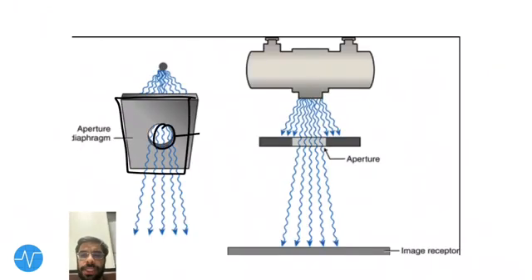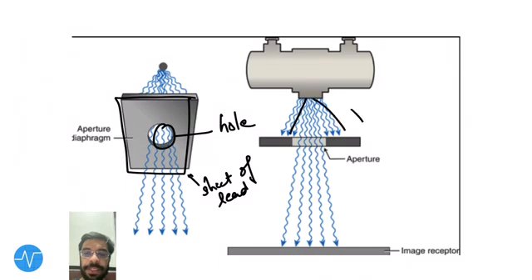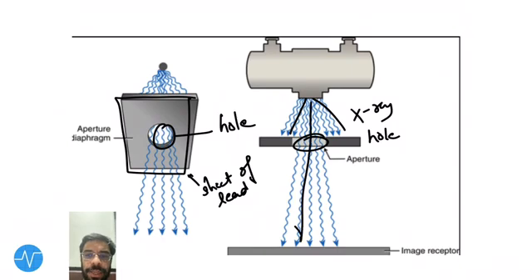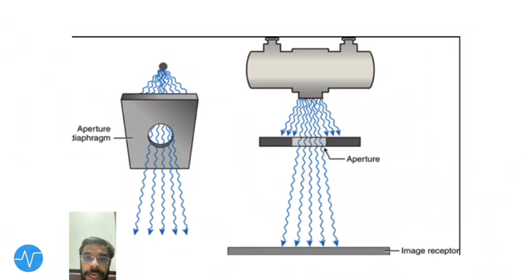Looking at the diagram: there is a sheet of lead with a hole. X-rays produced from the glass tube hit the beam restricting device, and only those x-rays aligned with the hole will pass through. This regulates and restricts the shape of the x-ray beam.